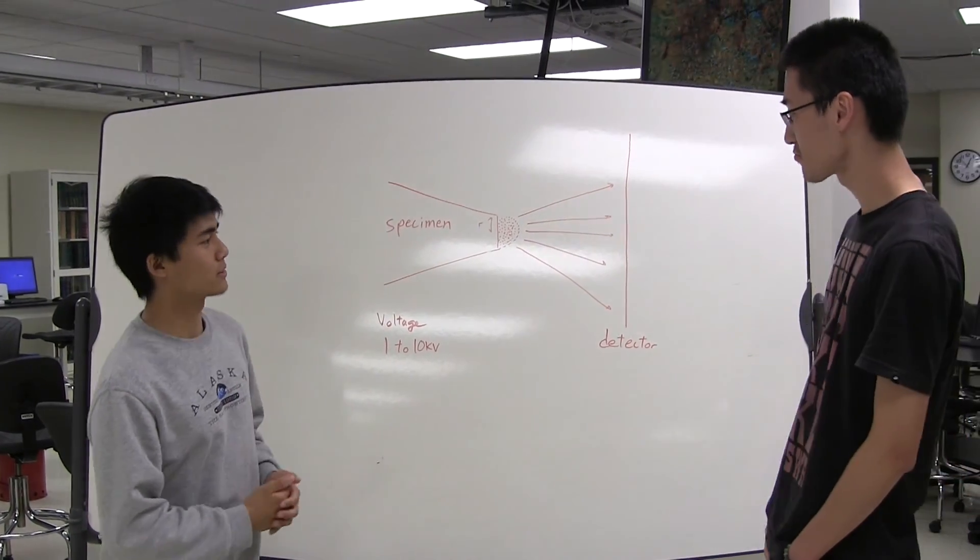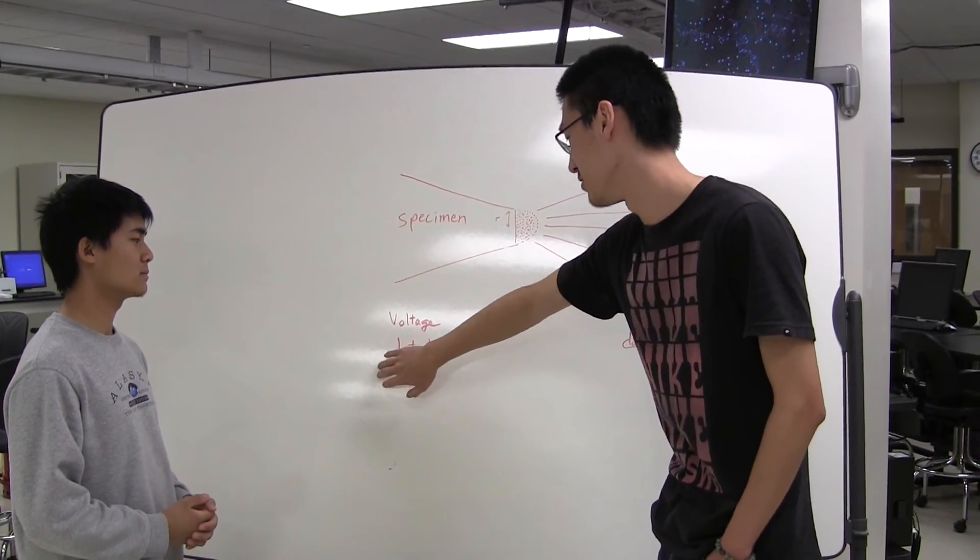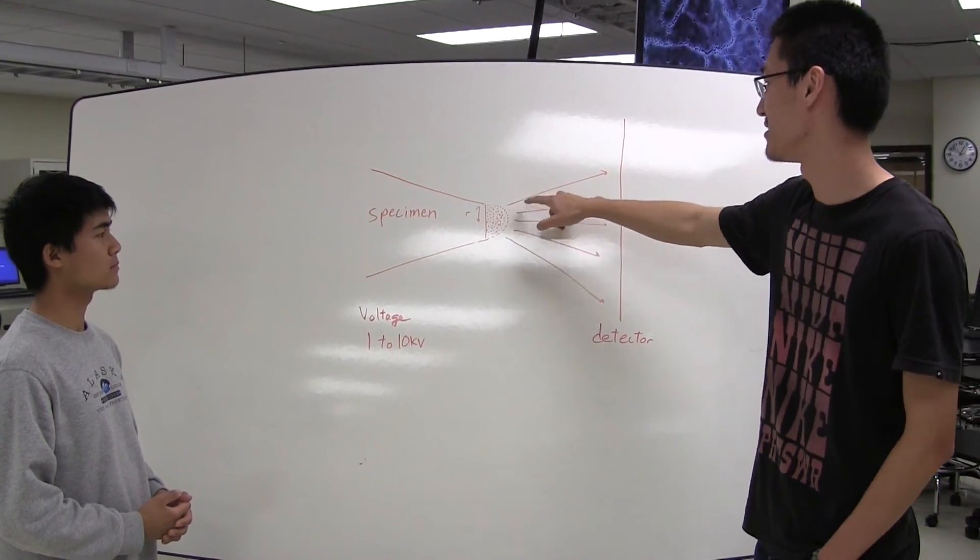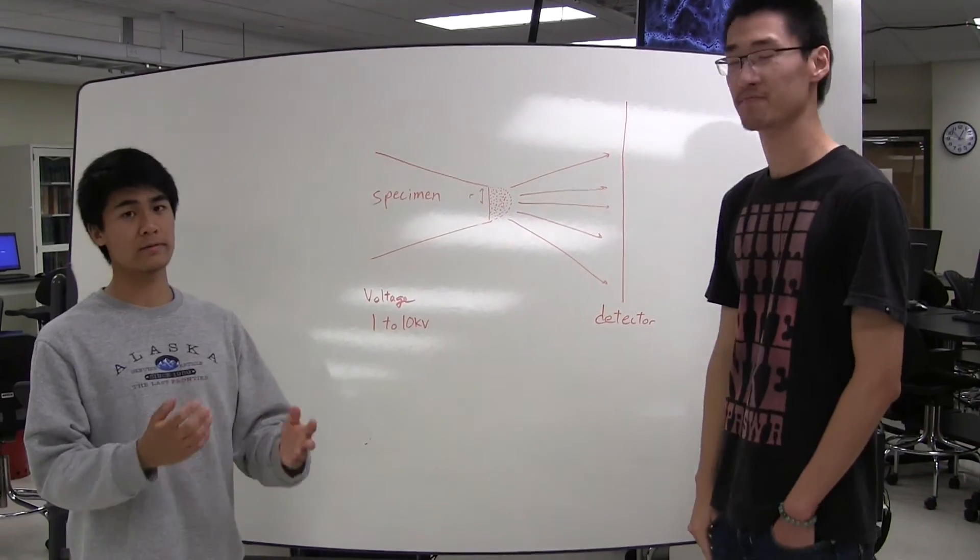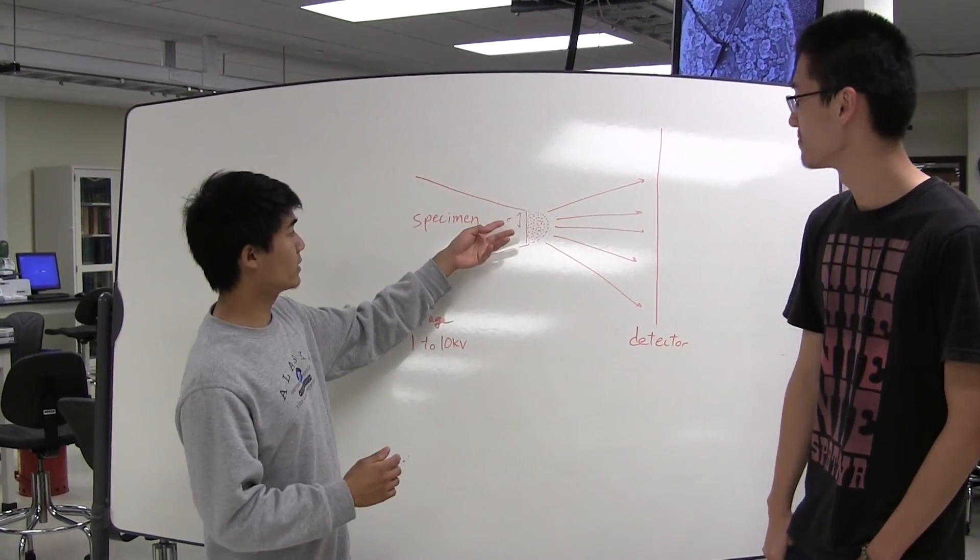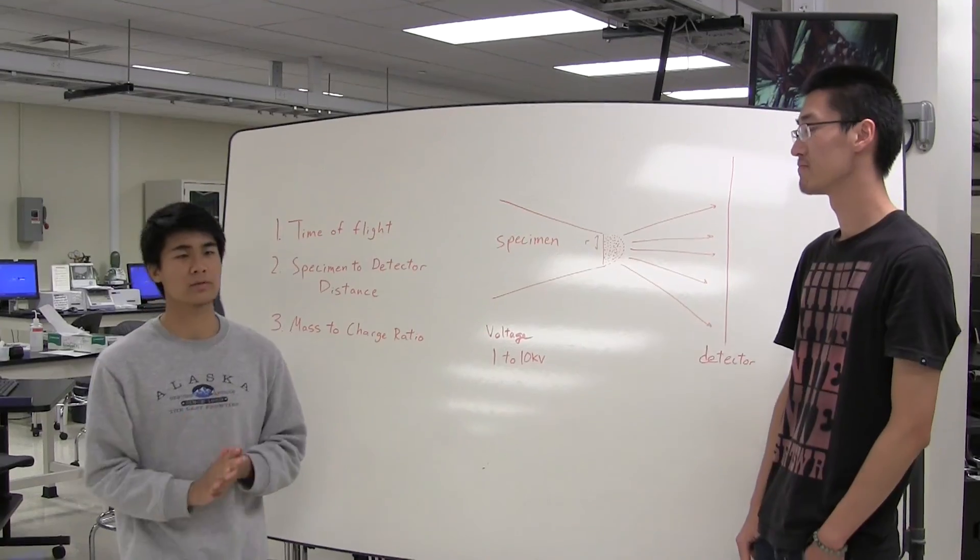So how does the atom probe work? Well, the atom probe will generate a voltage from 1 kilovolt to 10 kilovolt. And then the atom here will be ionized and hit the detector. In order for this to be successful, our specimen needs to be extremely sharp. The radius, as seen here, is typically about 50 to 100 nanometers.